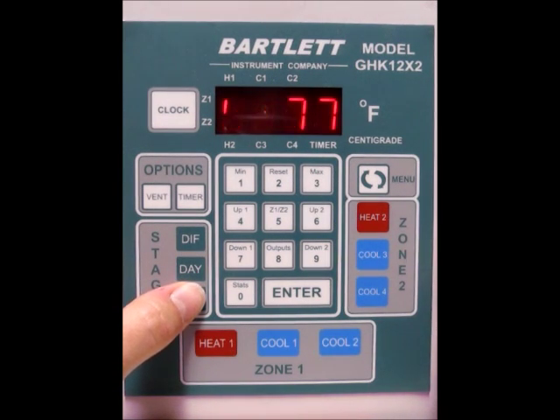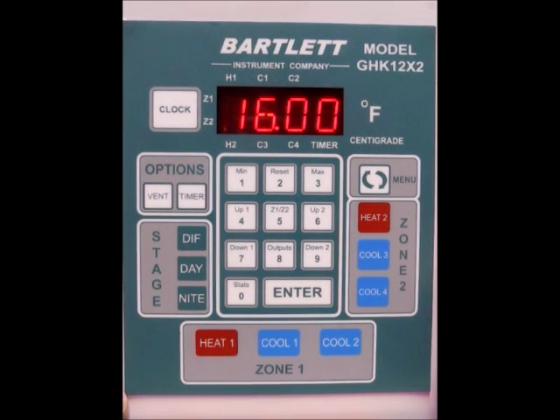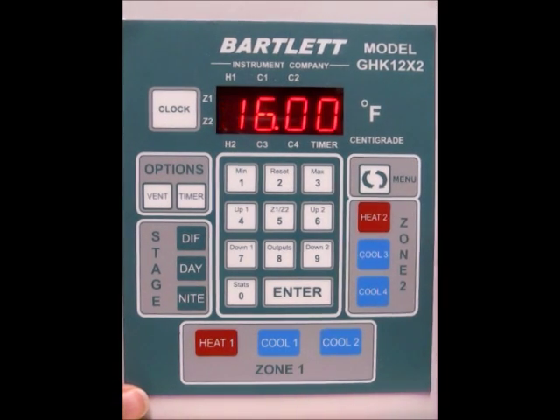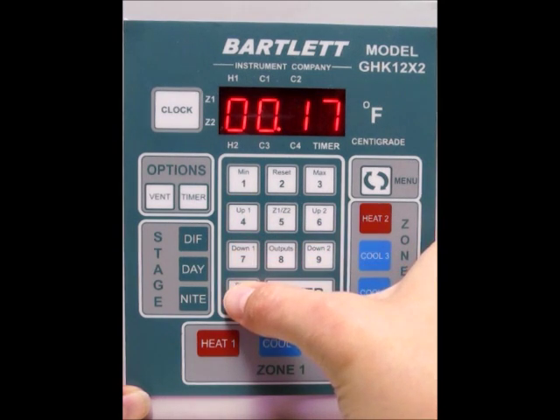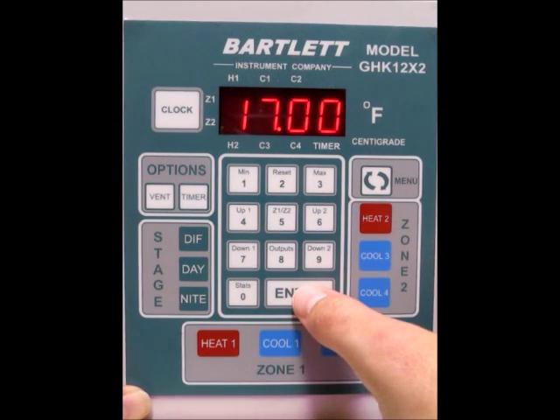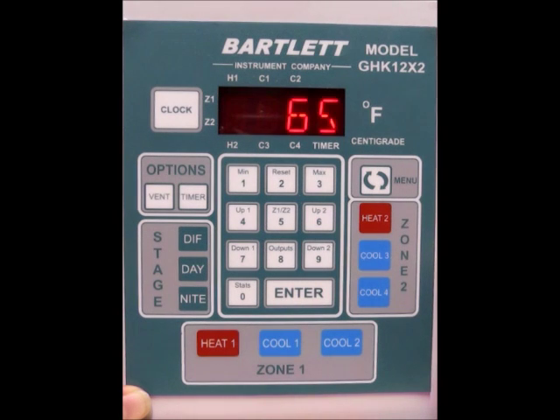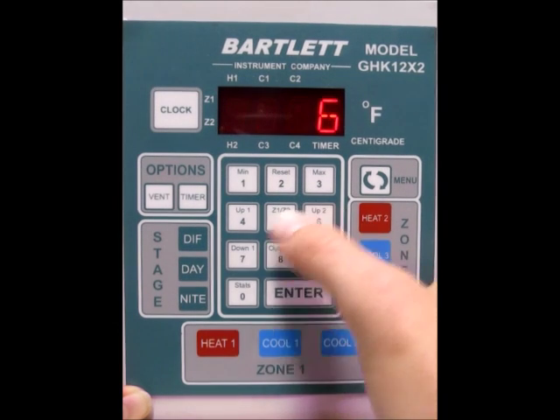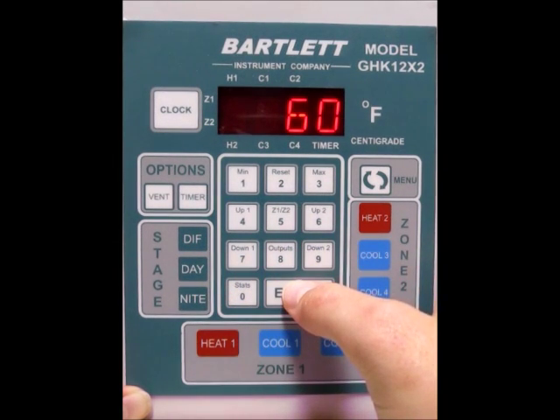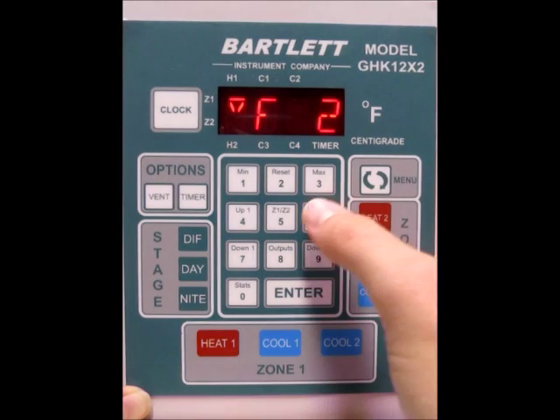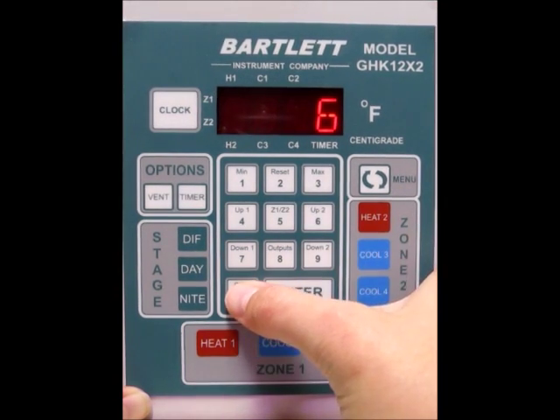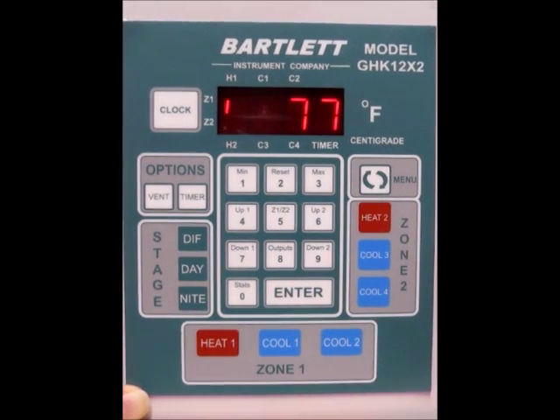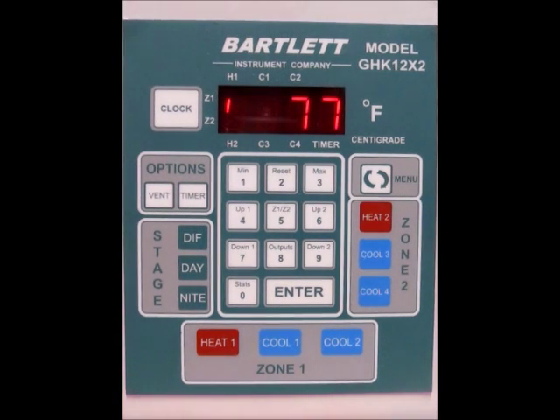Press the Night button. Right now it's set for 4 p.m. on the 24-hour clock, so I'm going to set it for 5 p.m. by typing in 1700 and pressing Enter. It's currently at 65 degrees — I want to go down to 60, so type in 60 and press Enter for zone 1. Zone 2 asks the same thing, so type in 60 and press Enter. Now we're back to normal operating mode.